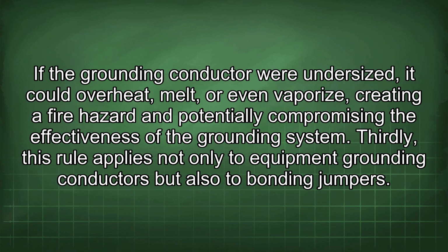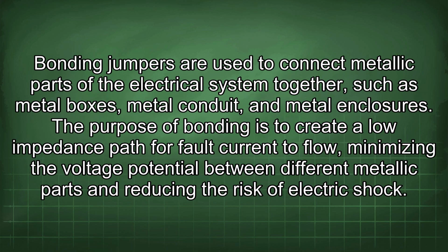Thirdly, this rule applies not only to equipment grounding conductors but also to bonding jumpers. Bonding jumpers are used to connect metallic parts of the electrical system together, such as metal boxes, metal conduit, and metal enclosures. The purpose of bonding is to create a lower impedance path for fault current to flow, minimizing the voltage potential between different metallic parts and reducing the risk of electric shock.